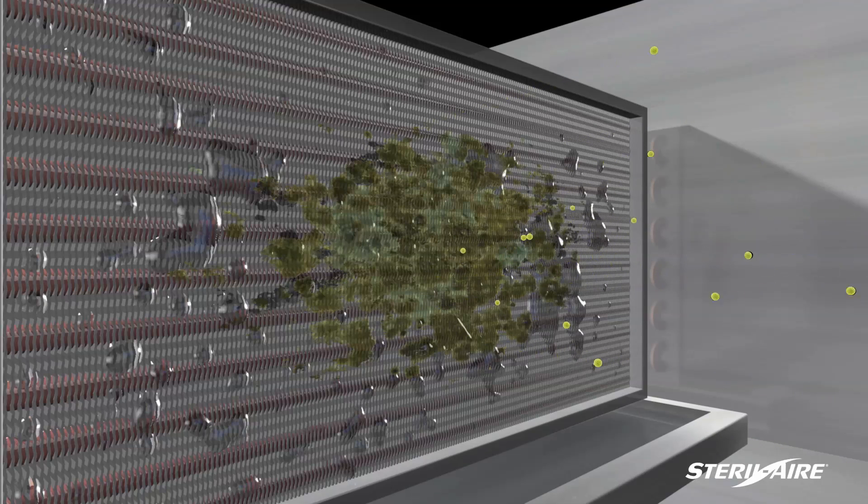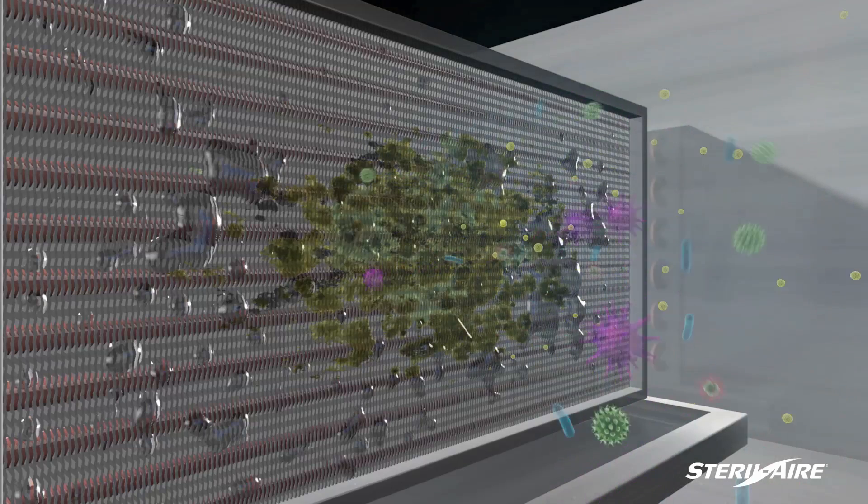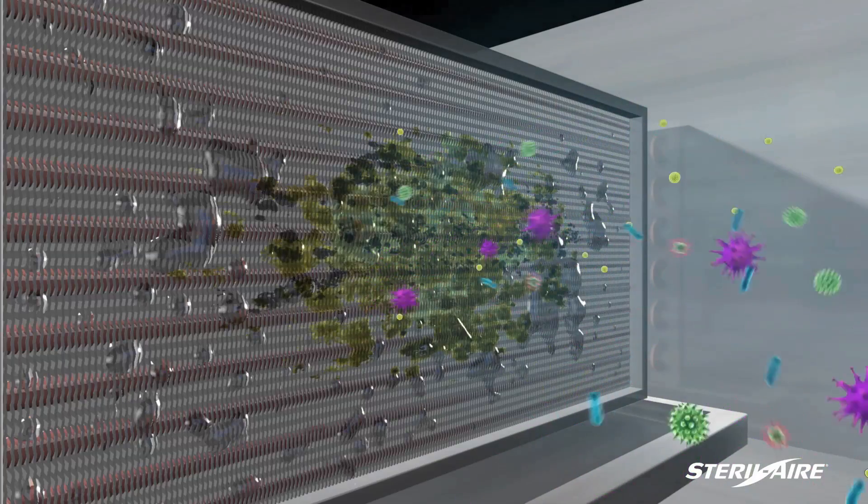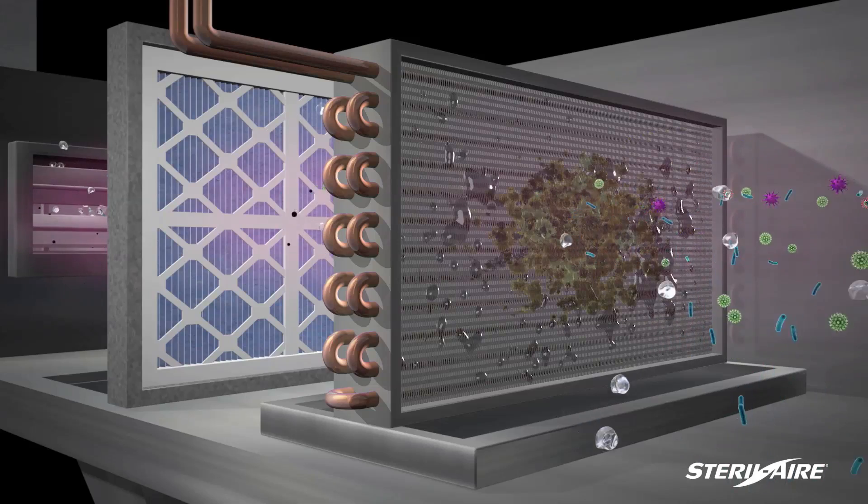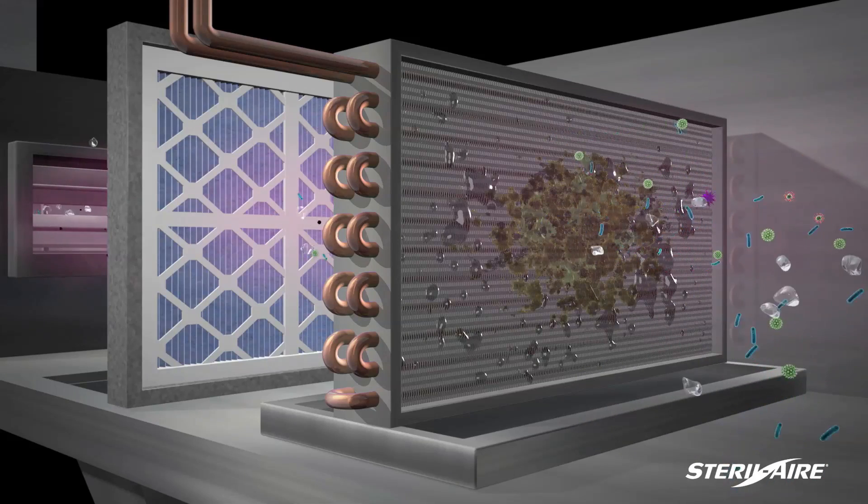Its sticky surface attracts and grips the dirt, forming the biofilm. The biofilm reduces the heat transfer function of the coil, and consequently the air is not cooled sufficiently, nor is the humidity removed.